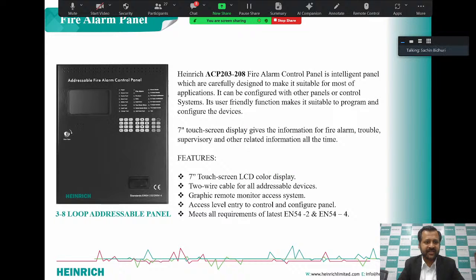This is the main panel, and as you can see, in this panel we have at most 8 loops, and each loop can have 250 devices connected to it. It has a 7-inch touch screen display. You can give addresses to all the detectors from the touch screen panel itself, and we have a programmer kit as well, with the help of which you can provide the address to all the devices connected in the loop. As you can see, it is a two-wire cable. Two-wire cable is required for addressable devices. It has access level entry to control and configure the panel, and it meets all the requirements of the latest EN54 certification.